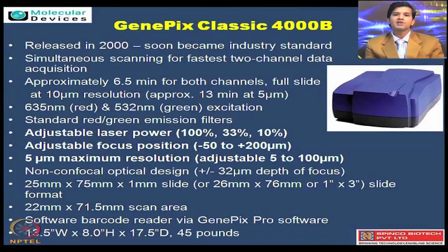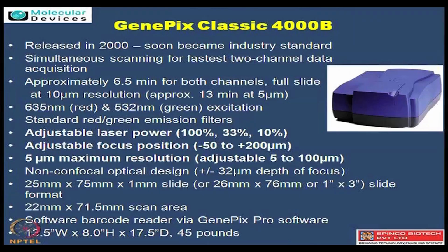The adjusted focal position is from minus 50 to 200 microns. This allows you to focus in different ways, so we can have different slide compatibility with the scanners. 5 micron resolution is the maximum it allows, and it can go up to 100 microns of resolution. It is using the non-confocal optical design, and any standard slide can be used for scanning, so it gives a wide range of applications.